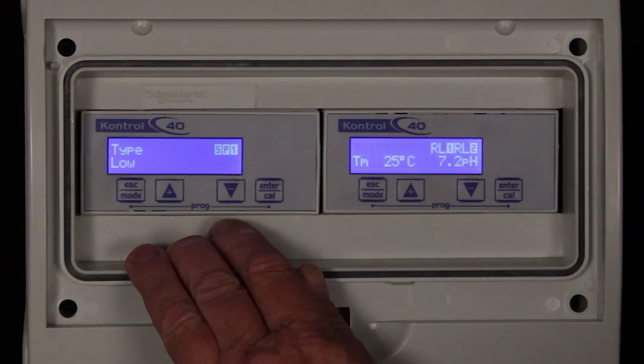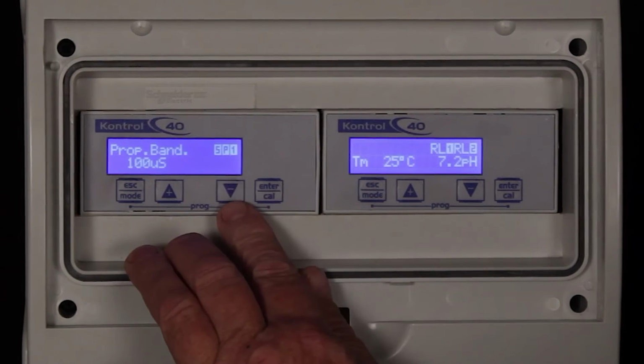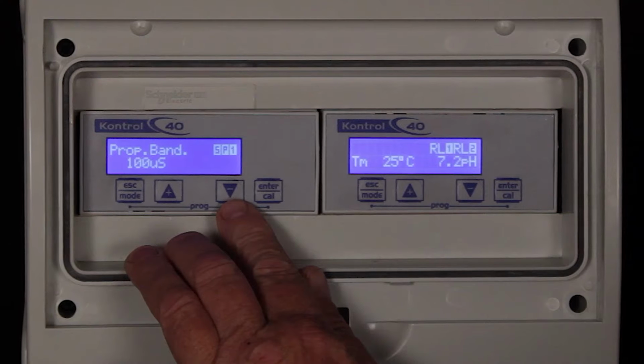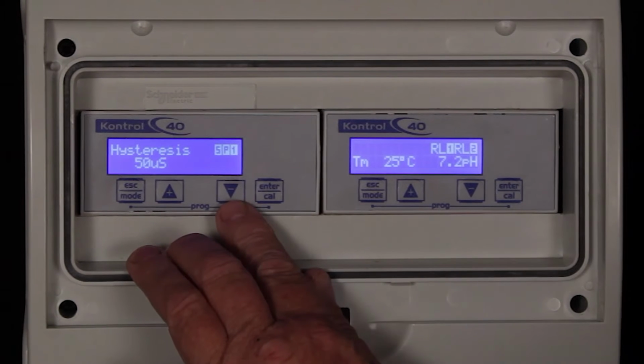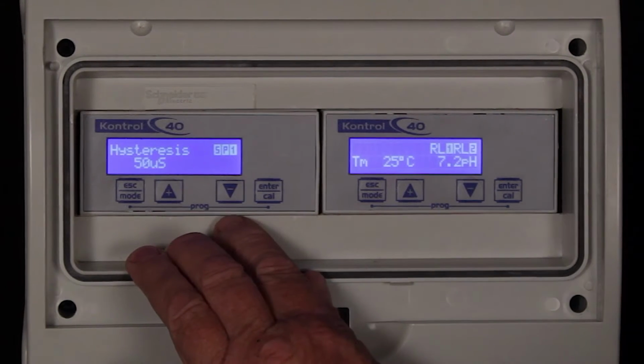Now press the down arrow and we go to the proportional band. For more information, please refer to the manual, page 7.3.5 for an explanation of this feature. For our application, I have turned this value to its lowest, which is 100 microsiemens. For hysteresis, we have set this to 50 microsiemens. So this means as soon as the actual value goes 50 microsiemens or lower than the set point, the EC pump will be switched on.